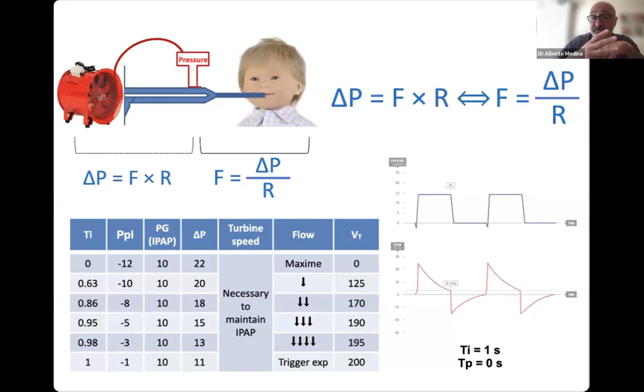So we have another concept included in this behavior, which is the ramp, the rise time, the slope. The slope, the rise time, the ramp is the velocity with which we change from the low velocity, so the low pressure, the EPAP, to the high pressure, the high velocity of the turbine, IPAP. But we need another parameter in this pressure support, which is another sensor that detects the diminution in the inspiratory flow, and this is the expiratory trigger. If we have a very good ventilator which can increase the alveolar pressure, but just during the inspiratory time, we are going to decrease the work of breathing, and this is the pressure support concept.